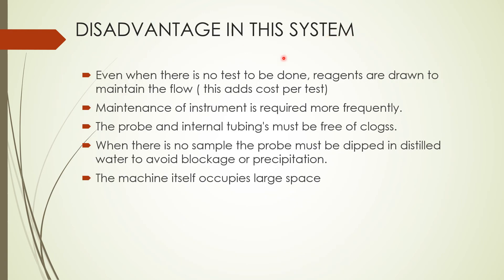Disadvantages of this system: even if there is no test to be done, reagents must be continuously drawn and the flow maintained, which adds cost. Maintenance of the instrument is required more frequently. The probe and internal tubings must be free of any clogs or blocks, and when there is no sample the probe must be dipped in distilled water to avoid blockage or precipitation. The machine itself also occupies large space.